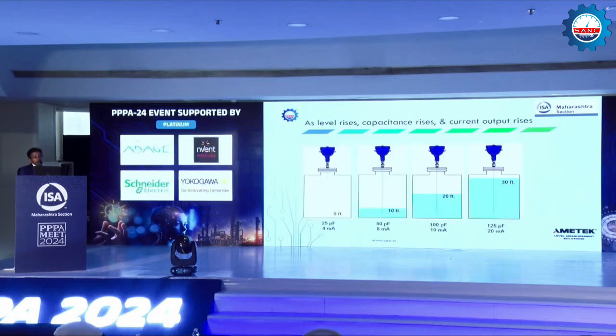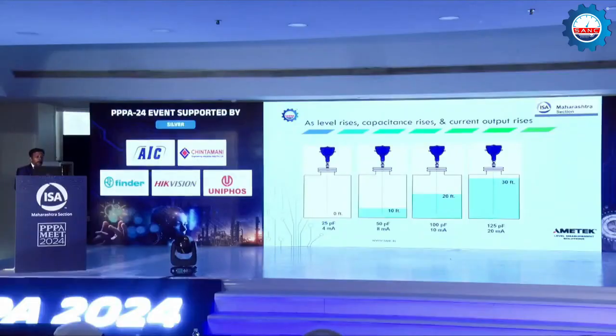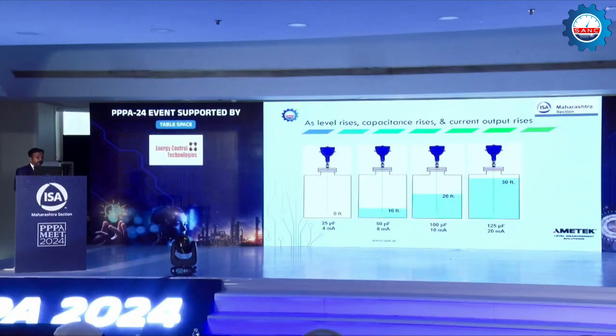This shows the installation of a level transmitter in an empty tank. In the first picture, in an empty tank, for example, we get 20 picofarad. We measure capacitance in picofarad. So we get 20 picofarad, and that is set as 4 milliamps, which is the zero level because there is no level. And then you pour some liquid, let's say water.